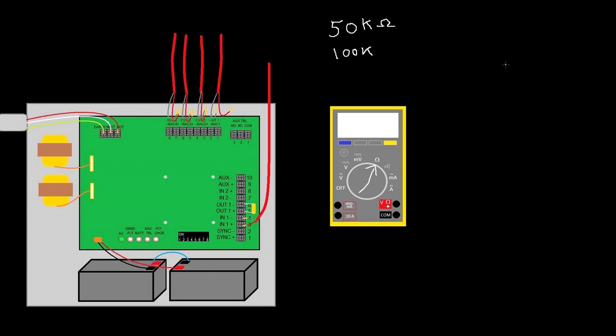There should not be continuity to ground on any of your circuits. It's good to get that threshold, maybe you start thinking in terms of okay, well anything over 500K I need to worry about. But if it shows up as a K, I think you need to worry about it.